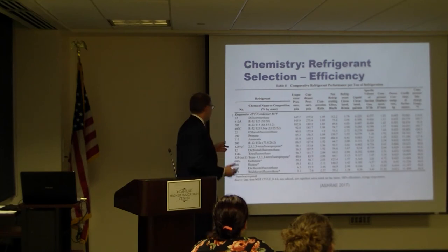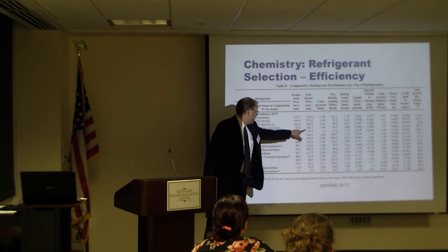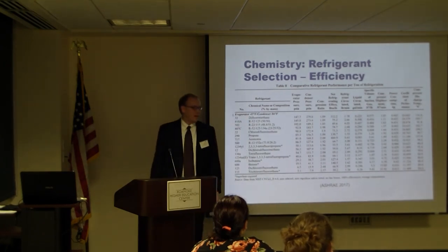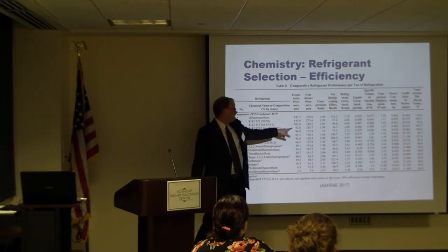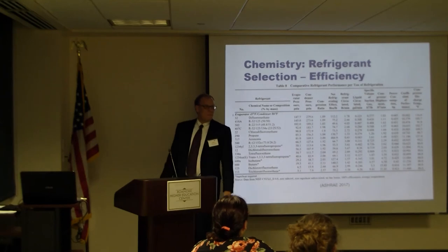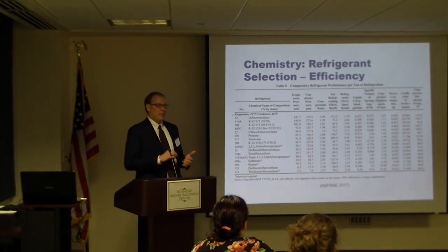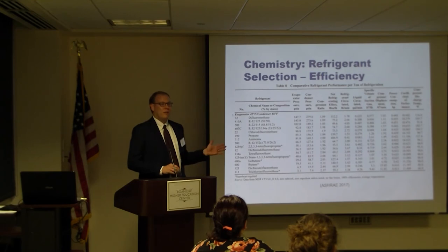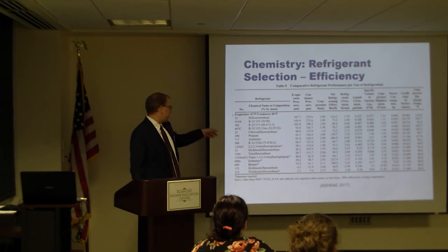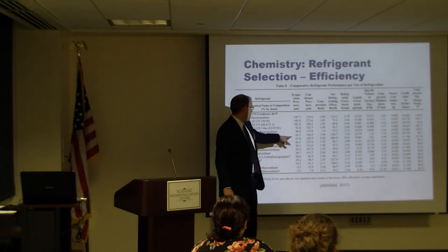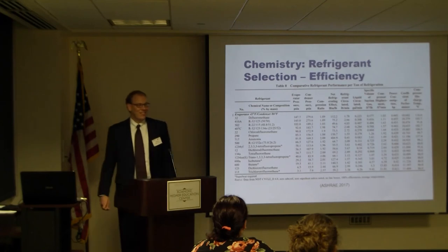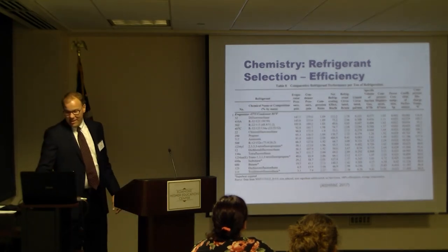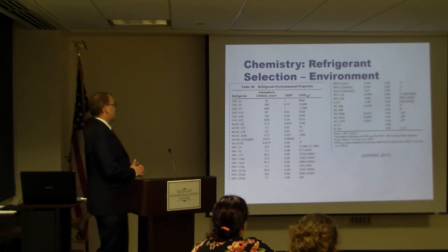The other thing to look at is the pressures. R12, R22, we ran at lower pressures, 180, 125 psi. A lot lower pressures the whole systems ran at. Now, with R410A, we're running close to 300 psi. That makes all of our equipment bigger, it makes the installation more complex. Everybody wonders, why do we have to replace all the refrigerant line sets? They're all designed for a maximum condenser pressure of 173 psi. Now we have to handle 275 psi. Everything's got to go.